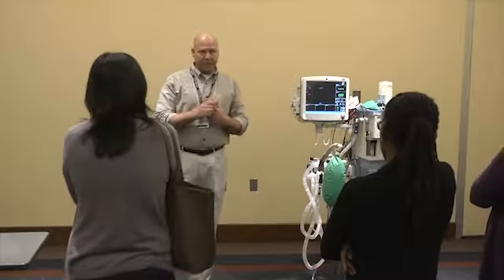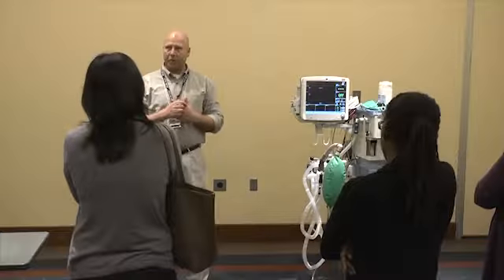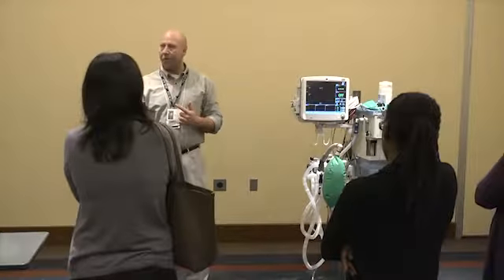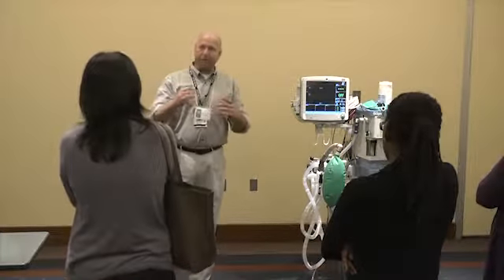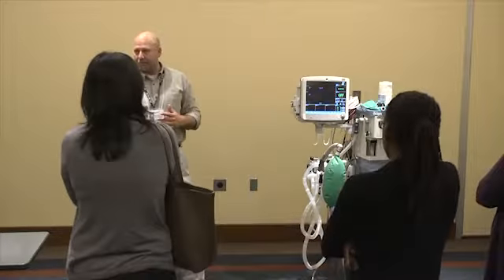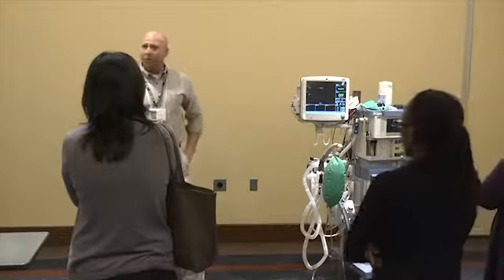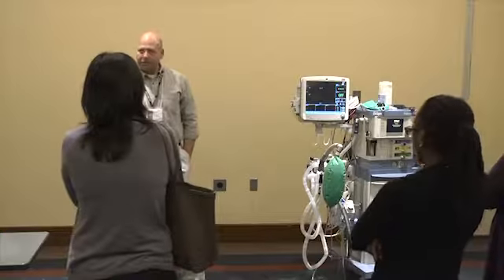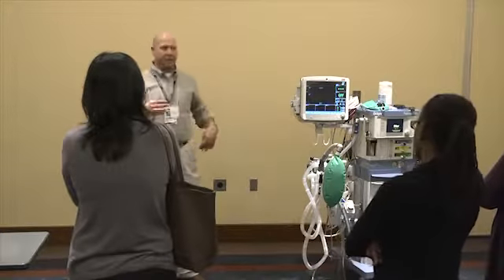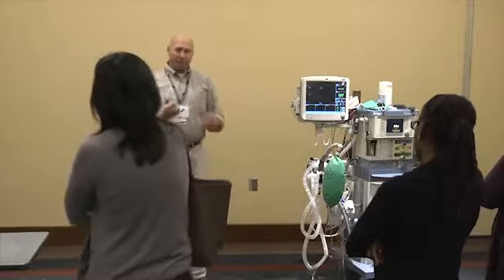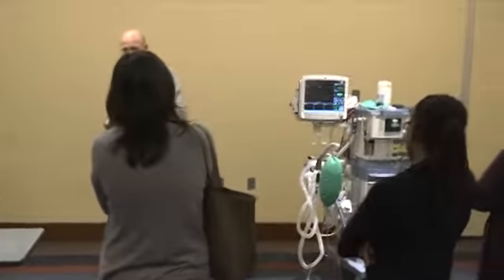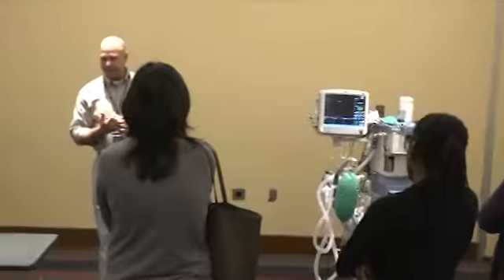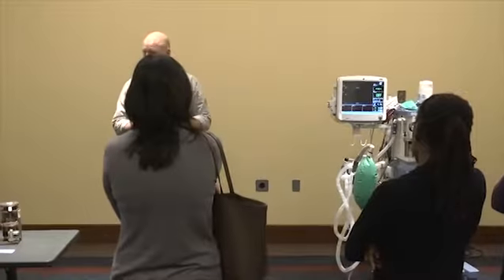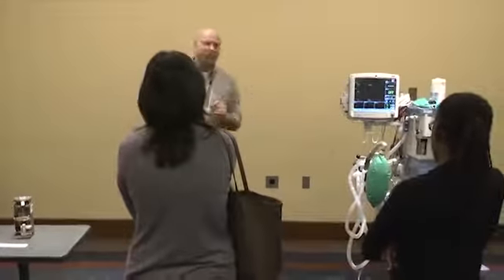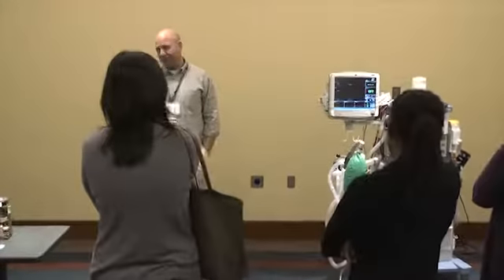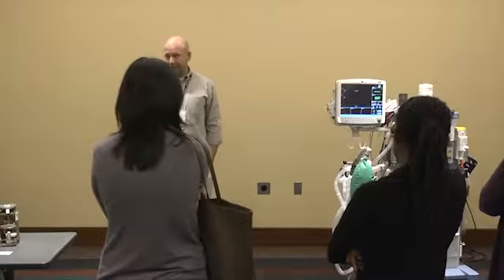Okay? So the first failure device on your anesthesia machine to protect against hypoxia is your oxygen failure protection device. The second protection device is your oxygen ratio controller, or ORC. And that is your proportioning device for the amount of nitrous you're delivering with your oxygen. So those are the two, OFPD, ORC. Now you're going to be asked, well, when does all this stop flowing? On the Narkomed GS anesthesia machine, the old series, at 36 PSI you will get an alarm letting you know you're losing your O2. On the newer ones, they do not alarm until you hit 16 PSI. So there's a difference there.